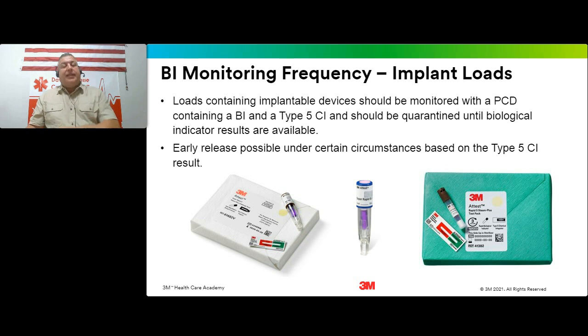AAMI has a document inside ST79 - it's the early release form. And the reason why we run the class, or the type 5 CI, is that it mimics the death curve of the BI - they're matched together. We're releasing, or we would early release if potentially needed, based on that type 5 indicator. And then hopefully shortly thereafter, we would get a readout, a negative readout of our biological.